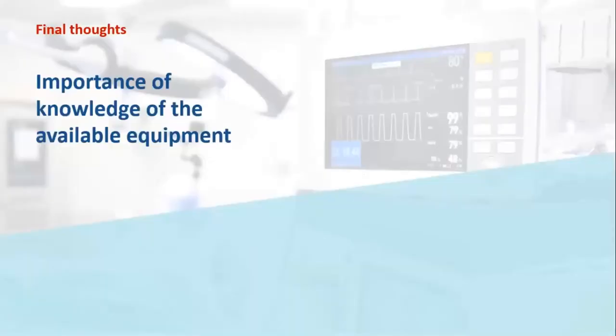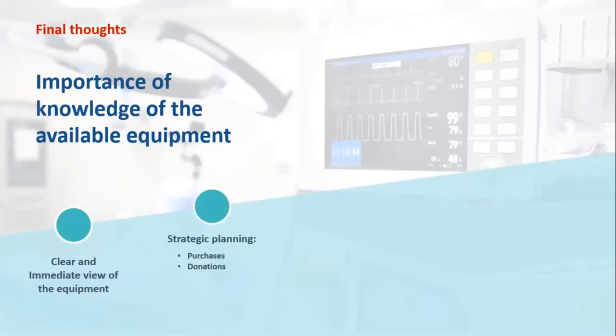All in all, we can say that a correct and updated inventory is the basis for the proper management of medical equipment, because as we saw earlier, first of all, we can have a clear and immediate view of the equipment. Then, having this knowledge, we can perform a strategic planning of future purchases or donations and only acquire what is truly needed.